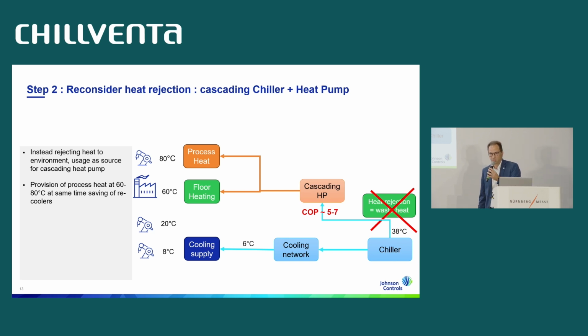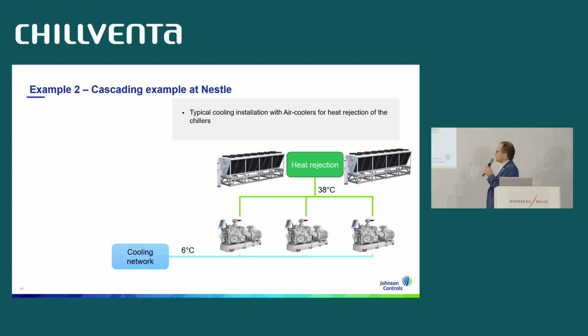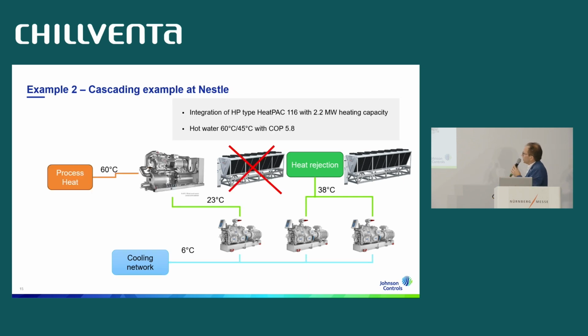And that's again not theory. I have an example here. So this is an example from our customer at the Nestle Werk in Bissenhofen in Germany. And this was the installation. So typically we have the chillers here, the chill packs, and a cooling network, and we have a heat rejection at 38 degrees Celsius. So what we have done here, we integrated a heat pump.